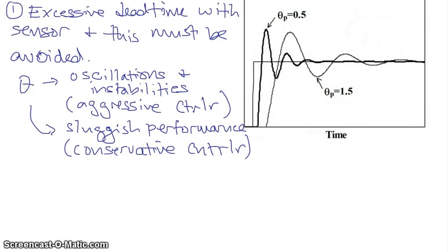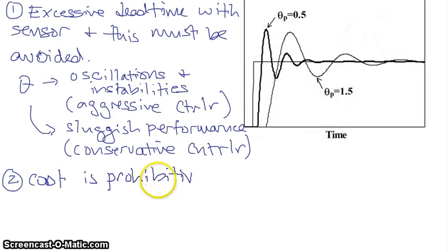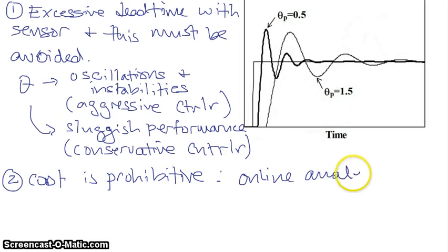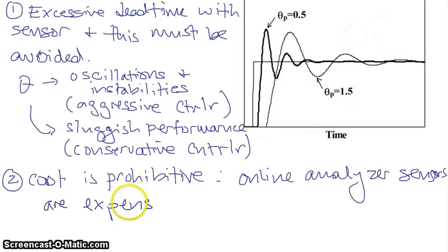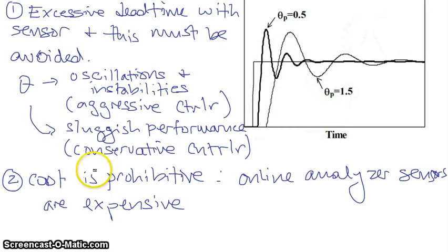Another reason to use inferential control is that your cost is prohibitive — your analyzer sensor may be very expensive. Online analyzer sensors are expensive, so this would be a reason why you would use inferential control. Both of these scenarios — excessive dead time and high cost — apply to analyzer sensors, because analyzer sensors can have excessive dead time and can be expensive. So in the case where your ultimate controlled variable is a composition, it is often advisable to use inferential control for these two reasons.